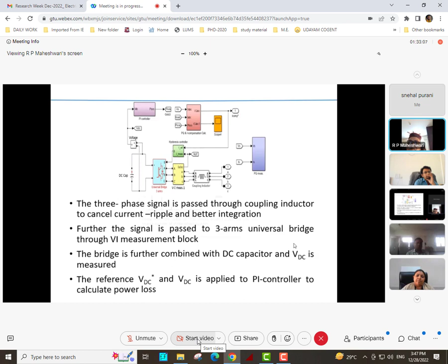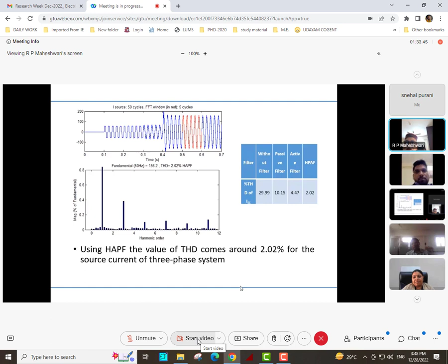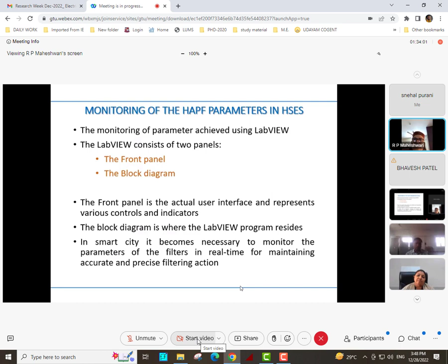Then some waveforms, what the harmonic filter is, and how the percentage THD is being reduced. Originally, without the filter, it was 29.99. Due to the passive filter, it got reduced to 10.1. With the active filter it reduced further to 4. With the hybrid passive active filter, it reduced to 2.02. In fact, this simulation was done using LabVIEW, so some LabVIEW panel aspects of this information are also shared.